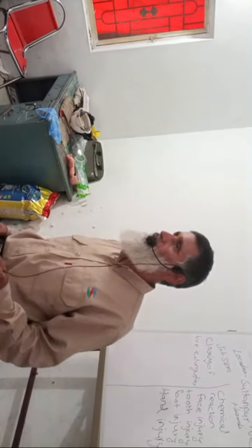Okay? And sometimes we use a fire hydrant. Mostly, we must keep a distance of 150 meters from fire hydrant to fire hydrant. We always keep this distance, we maintain the fire hydrants properly, and we check them. Monthly we test them to see whether they are working properly. These are things we continue to check. When taking the fire hydrant, a trained person can apply it. Here is the fire hydrant, this is the fire hydrant part.